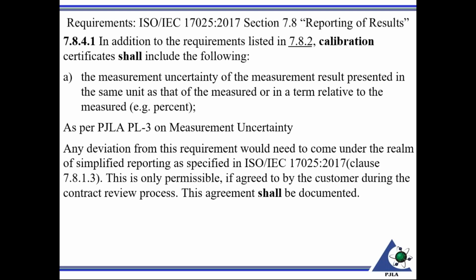Moving on to 7.8.4.1, this is calibration now. This section for calibration basically says the calibration certificate shall include the following: the measurement uncertainty of the results presented in the same unit as the measurand or in a term relative to the measurand. So when the standard was revised in 2017, this used to say, shall report the measurement uncertainty and/or a statement of compliance. That and/or went away when the standard was revised in 2017. So this is pretty straightforward. As per the standard 7.8.4.1, the calibration lab shall report the measurement uncertainty. No more and/or a statement of compliance.